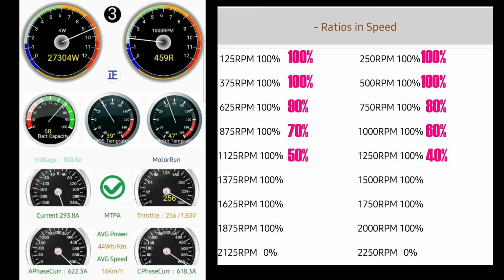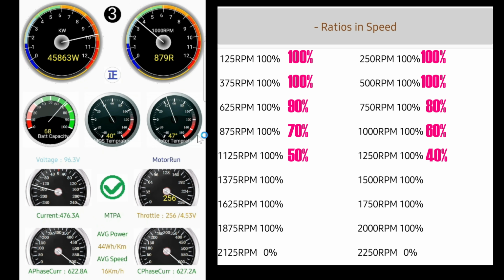I can get away with almost half here, probably 52 or 53%. So it's not going to hurt me to limit these things in ratio and speeds, even down to lower RPMs, but it will hurt me to limit the line amps. So we said 70% on 875 RPM. Let's go look at 875. There's 879, and it's still 622. 622 divided by 1200, that's 51%. I could go all the way down to 51% and not limit myself at 875 RPM, but we're going to only go to 70%. So we shouldn't be limiting ourselves by doing this.